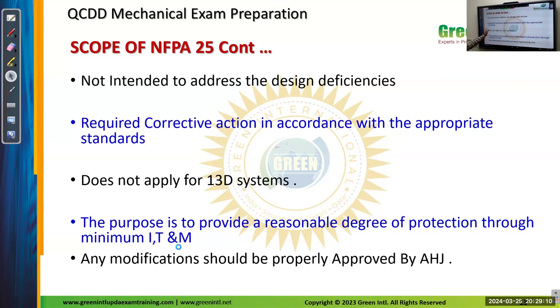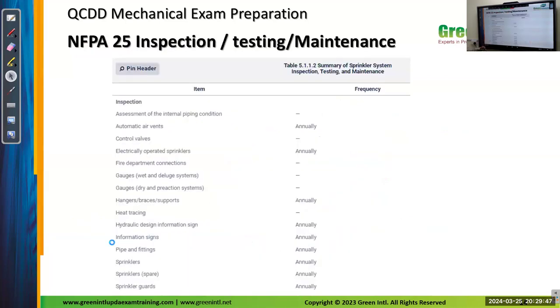Required corrective action in accordance with the appropriate standard does not apply to 13D systems. What is a 13D system? Sprinkler system for... in this system it is there, only 13 is there. And a figure 13 A, B, C, and D. Okay, I don't remember what it is. The purpose is to provide a reasonable degree of protection through minimum inspection, testing, and maintenance. Any modification should be properly approved by Qatar Civil Defense.